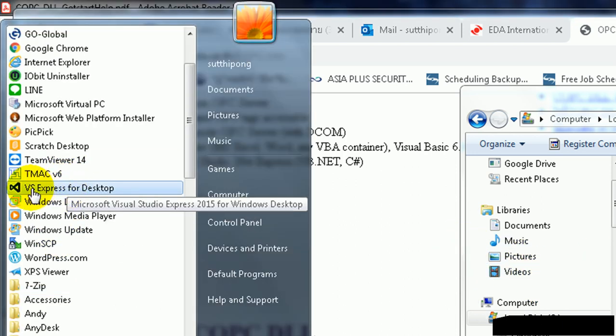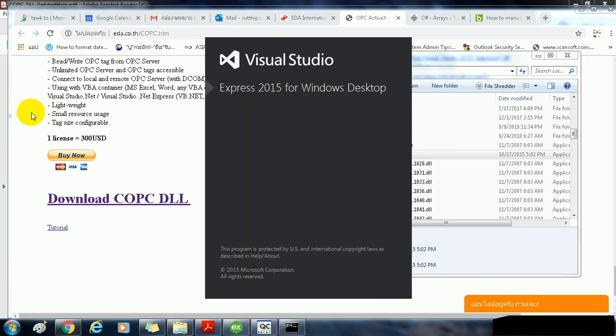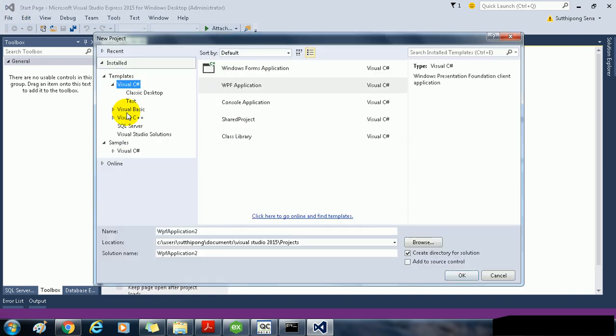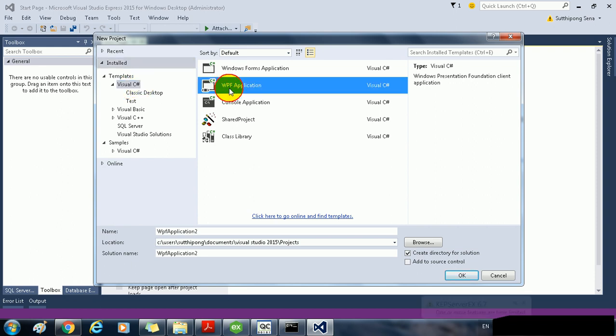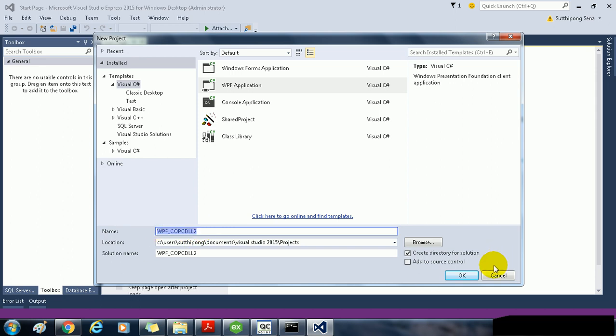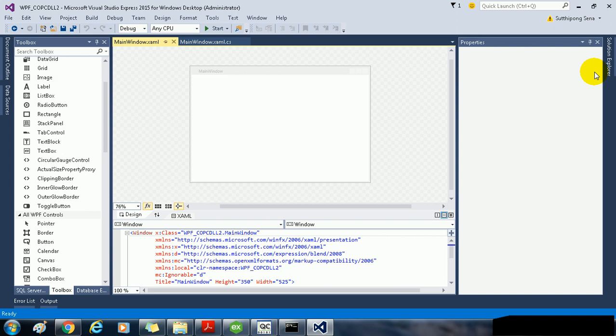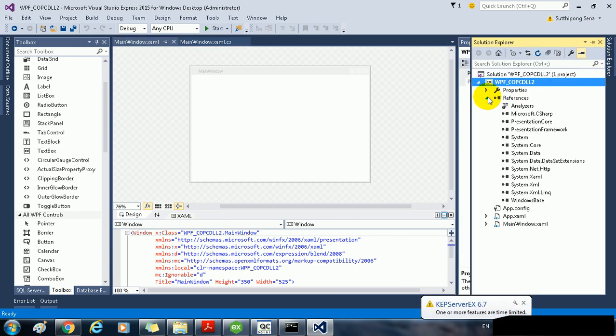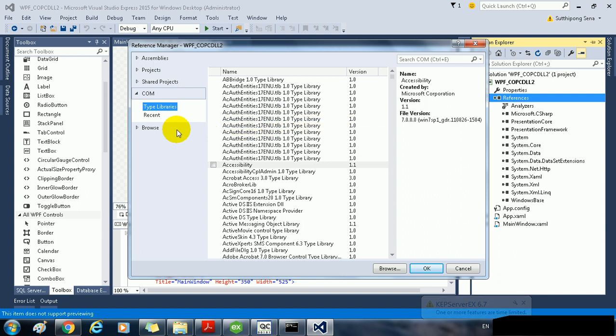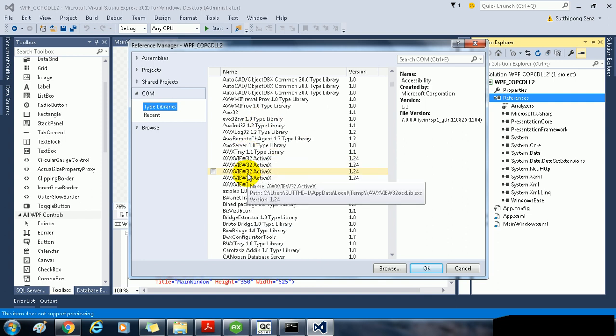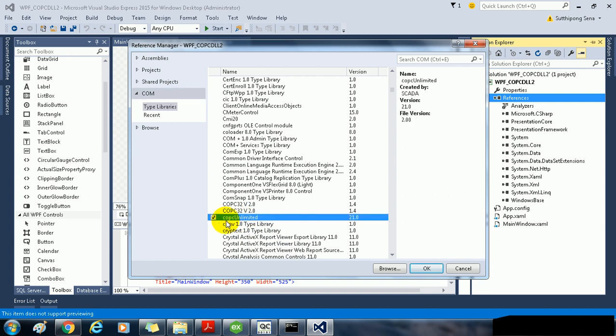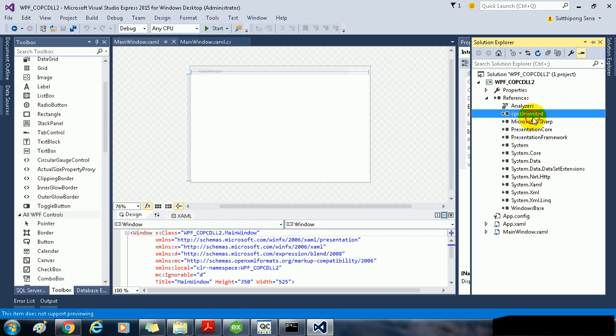After register the COPC DLL, create the new project on Visual Studio Express or Visual Studio Standard for desktop. Go to new project. In this example, I will use the Visual C sharp and the WPF application. Type the name of the project and then OK. Now go to solution explorer and reference. Right click on reference, add reference. Add the COM list. Search for COPC Unlimited. Check it and then hit OK.